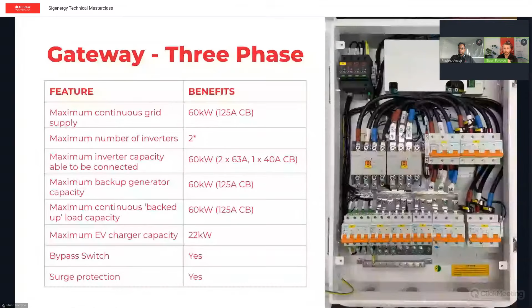Number five: how is the Sigenergy gateway wired? Firstly, on the inside door of each gateway there's a line schematic diagram showing how the system is wired, which is great for both new installs and when coming to a site to work out what's going on. They have labeled glands on the bottom of each enclosure - you can see 3 glands here, but there are 5, and they align with the switch gear it's running into, labeled accordingly. For example, this gland on the left says grid supply, and it's an appropriately sized gland, pre-installed, going straight into your main supply breaker. It's all pre-labeled, so it's very easy to see how things are wired up.